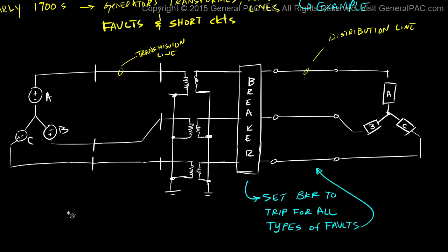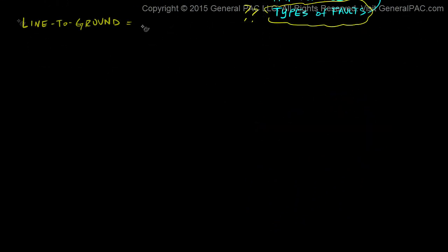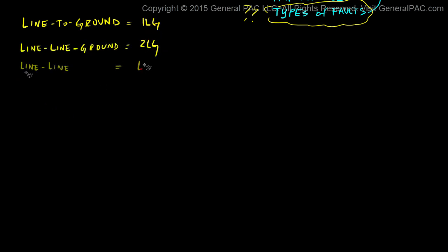As a power systems engineer, we are asked to set the circuit breaker so it trips for all types of faults on the distribution line feeding our load. We are given our system parameters, like line impedance. The question comes up: what does 'all types of faults' mean? In the power system, there can exist a line-to-ground fault, a two-line-to-ground fault, a line-to-line fault, and lastly, a three-phase fault.